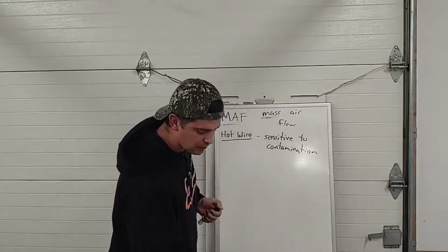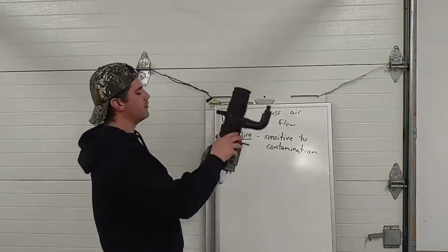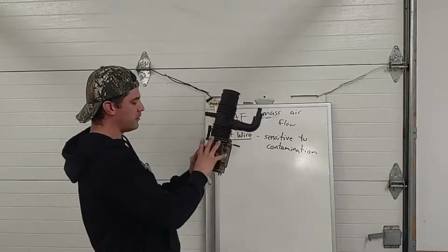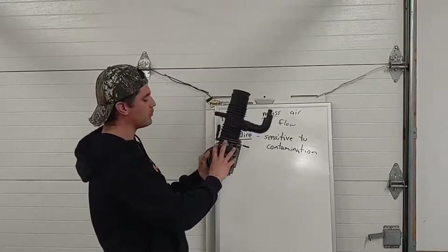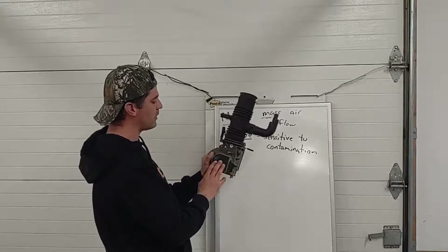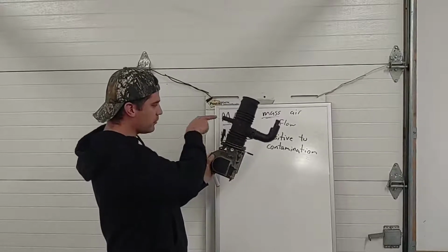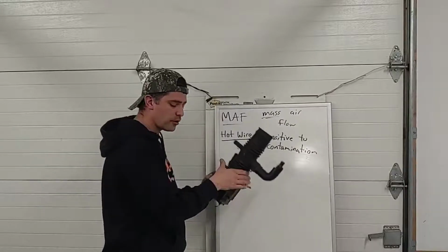The other thing that will report a false signal is if you have an air leak in this duct. So if this is your airflow sensor, no matter what kind it is, whether it's an old vane sensor, a vortex, or a hot wire, if you've got air sneaking in after the sensor, that's known as unmetered air.